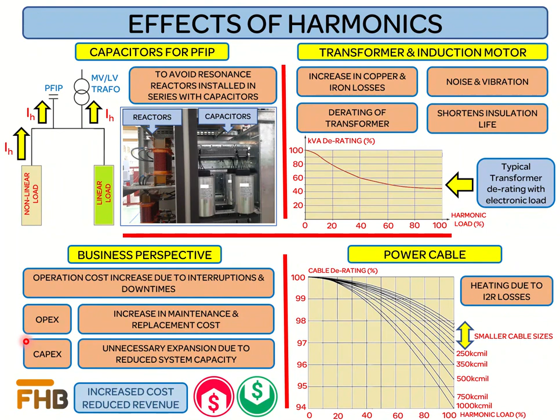A number of techniques can be used to limit the propagation of harmonics in the power system. A simple way of doing this is to segregate the load as linear and nonlinear and supply these loads through different transformers. The delta-star configuration, which is widely used in distribution transformers, has the property to eliminate the third order harmonic. However, all other harmonics do propagate towards the upstream network.